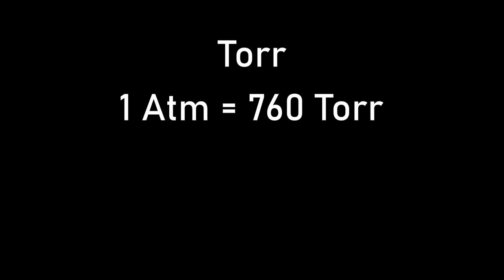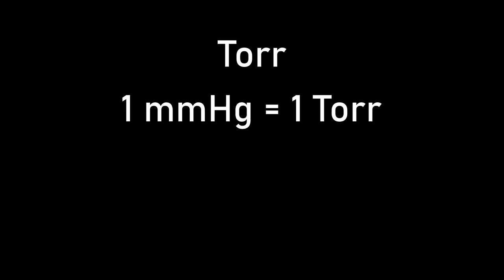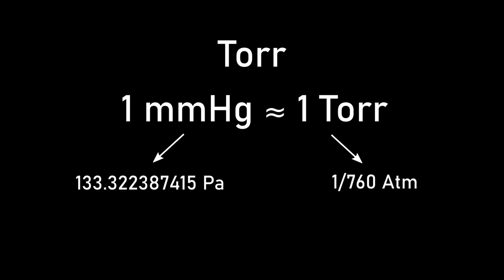The millibar is a far more common unit of measurement on both vacuum gauges and vacuum equipment datasheets. The other most common unit of measurement for vacuum is the torr. The torr is defined as being 1/760th of a standard atmosphere. Although this is a modern redefinition, it was originally intended to represent 1 mm of mercury, or the extra pressure generated by a column of mercury 1 mm high. In fact, the mm mercury has itself been redefined, and so the two units have drifted apart from their original equivalents. That said, the relative difference between these two units is so small that in most cases they're still considered equivalent.